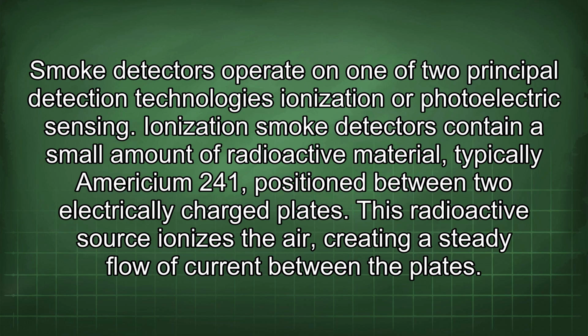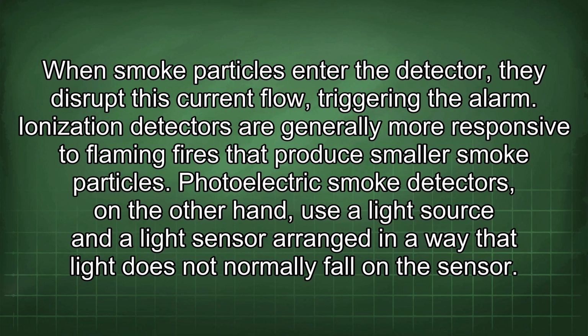Ionization smoke detectors contain a small amount of radioactive material, typically americium-241, positioned between two electrically charged plates. This radioactive source ionizes the air, creating a steady flow of current between the plates. When smoke particles enter the detector, they disrupt this current flow, triggering the alarm. Ionization detectors are generally more responsive to flaming fires that produce smaller smoke particles.